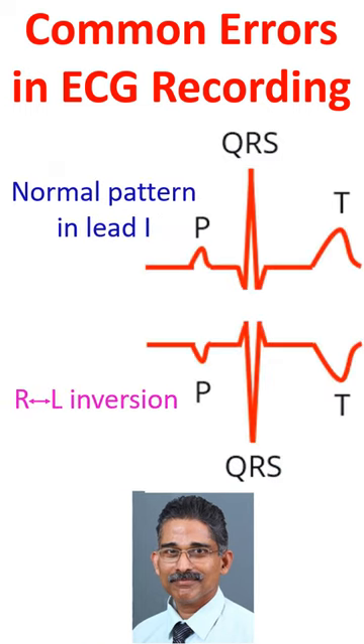Of these, the most common one is placing the electrode meant for the right arm in the left arm and vice versa. This will cause the waves which are expected to be upright to be inverted.